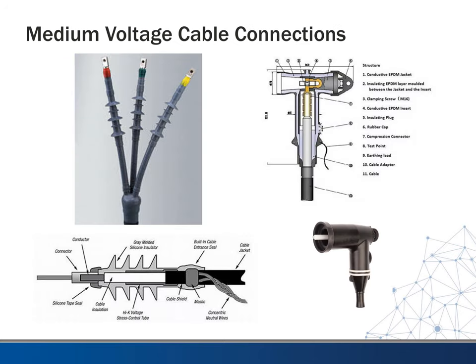One other thing worth noting is that with smaller wires, you usually just strip them and put them under a terminal. It's not that simple with medium voltage cable, because of the fields, the buildup, and the semiconductor layers involved. We have to use a more built-up connector called a stress cone. These are referred to as stress cones because they deal with electrical stress — a high voltage stress control tube. It's a little involved to terminate these and requires electricians to be familiar with the process, as it is more labor intensive.